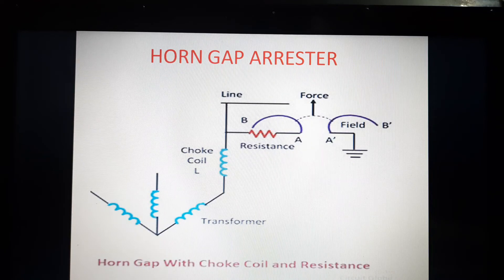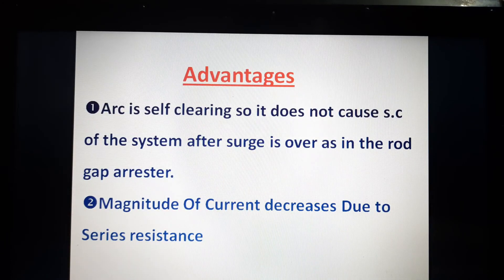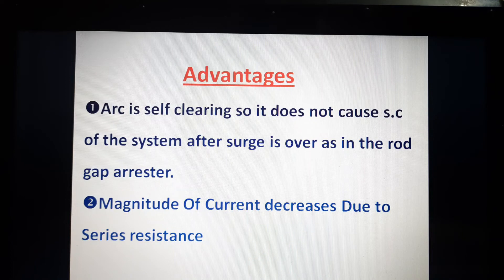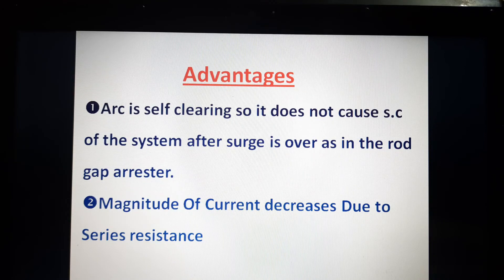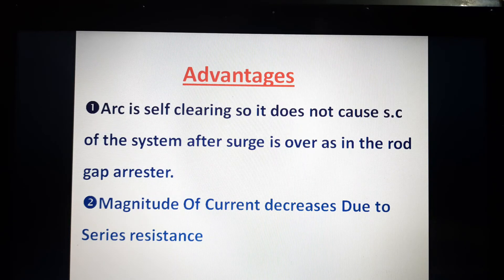The advantages of the horn gap arrestor are: first, the arc is self-clearing, so it does not cause a short circuit of the system after the surge is over — unlike the rod gap arrestor where a small voltage is sufficient to maintain the arc. In the horn gap arrestor, a very high voltage is required to maintain the arc. Second, the magnitude of the current decreases due to the series limiting resistance.